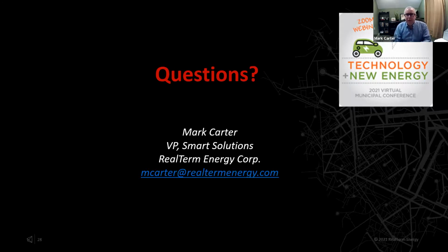The artificial intelligence, the 'brain' so to speak, is actually hosted in a cloud environment and then accesses the local building controls. You're not adding any sensors—it uses whatever sensors the building currently has. So if you've got rooftop units, VAV boxes, all those control points and sensor points are being aggregated, but no additional sensors are added to the building. So there's no cost or installation effort required there—you're merely utilizing your existing network as it is.